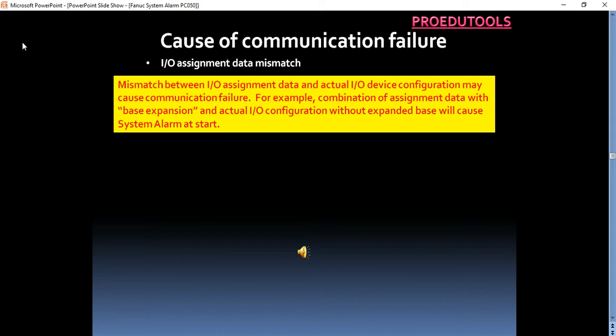IO assignment data mismatch. Mismatch between IO assignment data and actual IO device configuration may cause communication failure. For example, combination of assignment data with base expansion and actual IO configuration without expanded base will cause system alarm at start.